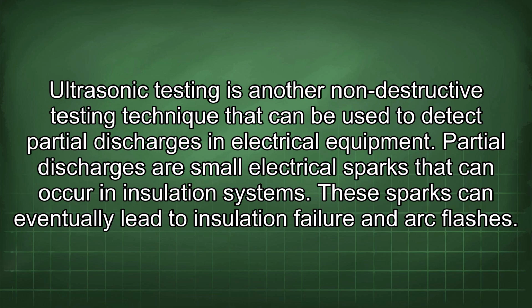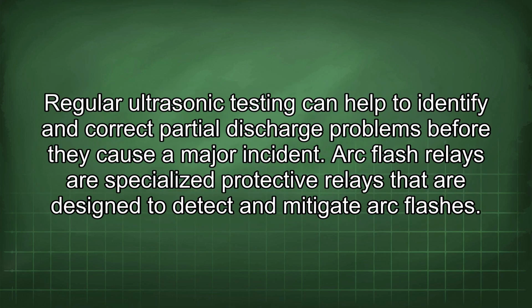Ultrasonic testing is another non-destructive testing technique that can be used to detect partial discharges in electrical equipment. Partial discharges are small electrical sparks that can occur in insulation systems. These sparks can eventually lead to insulation failure and arc flashes. Regular ultrasonic testing can help to identify and correct partial discharge problems before they cause a major incident.